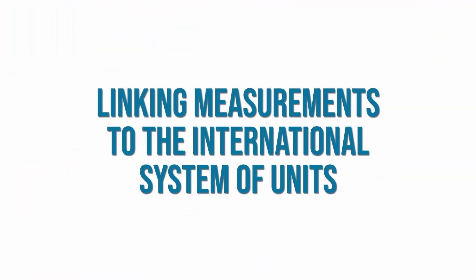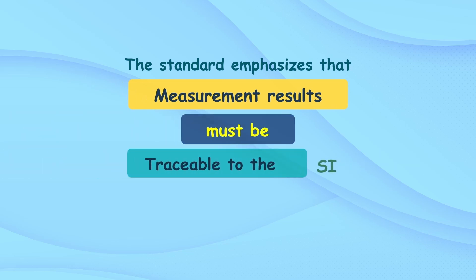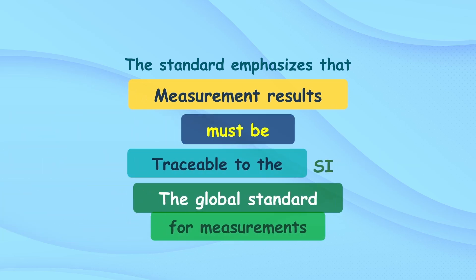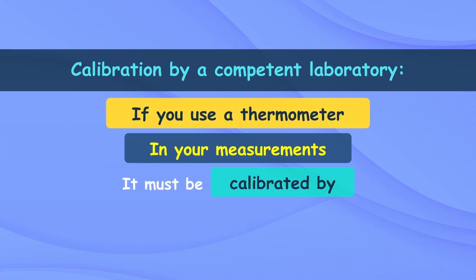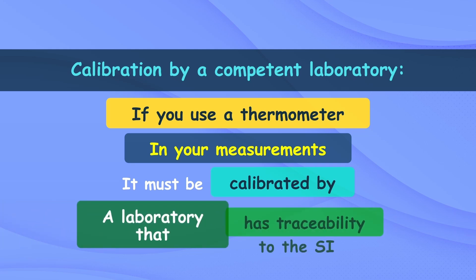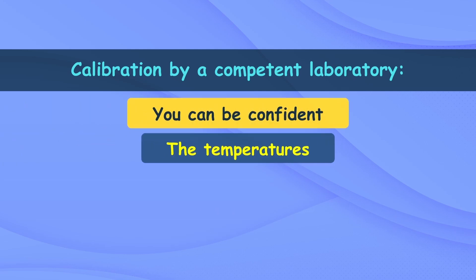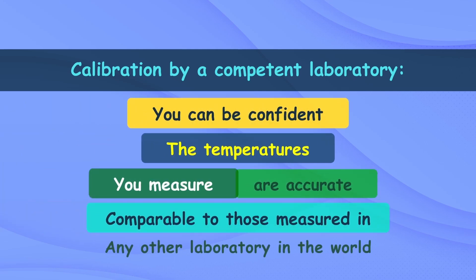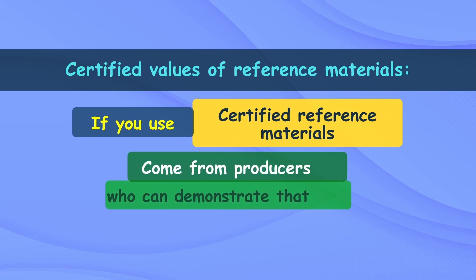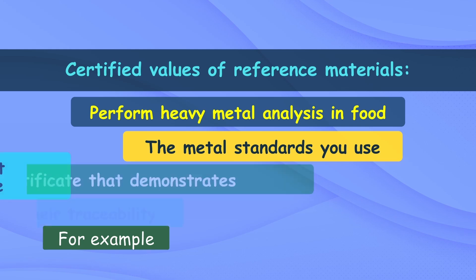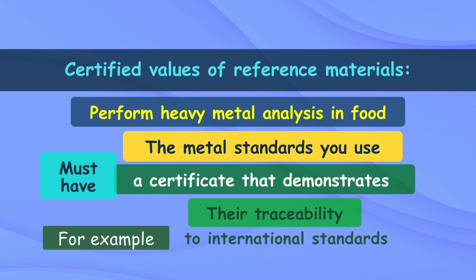The standard emphasizes that measurement results must be traceable to the International System of Units. This traceability can be achieved in several ways. First, calibration by a competent laboratory: if you use a thermometer, it must be calibrated by a laboratory with traceability to the SI, ensuring your temperatures are comparable to those measured anywhere in the world. Second, certified reference materials must come from producers who can demonstrate traceability to the SI — for example, metal standards used in heavy metal analysis in food must carry certificates demonstrating traceability to international standards.